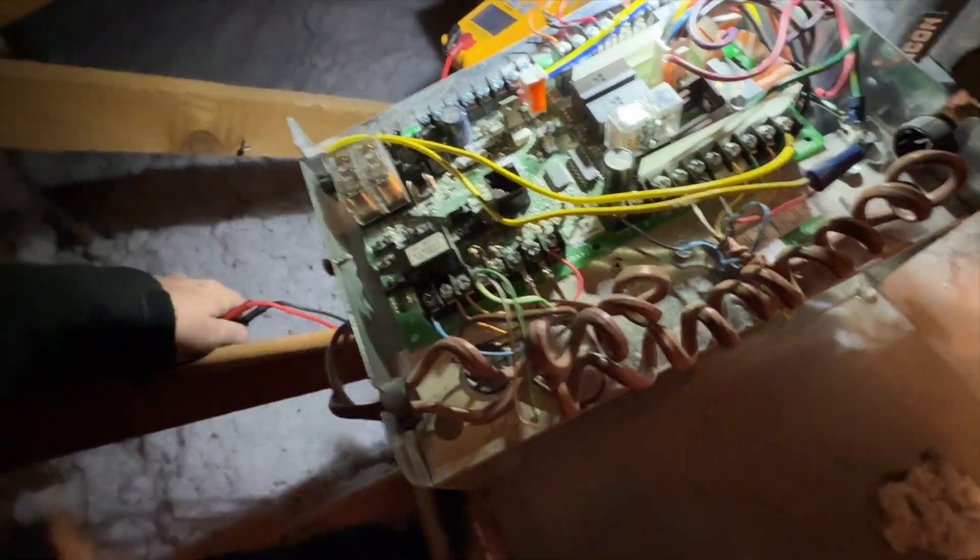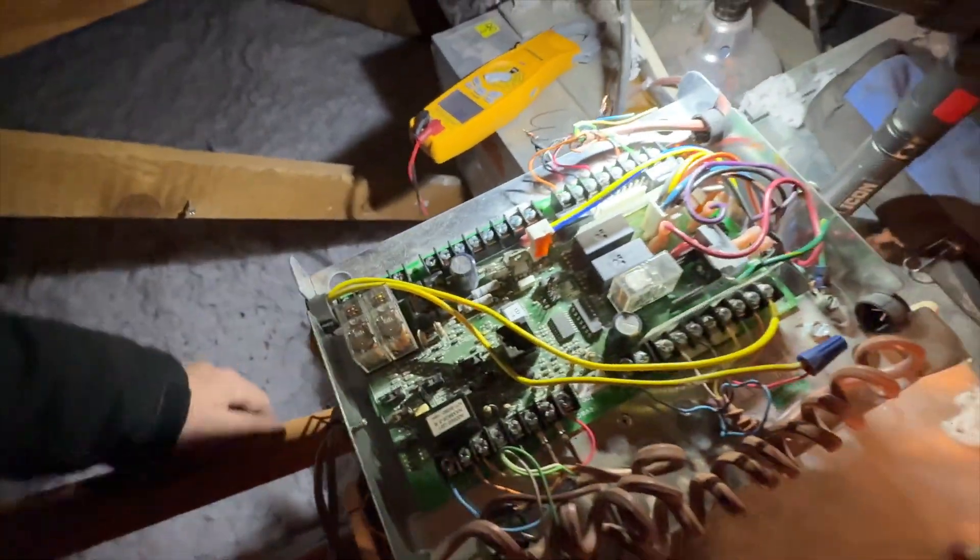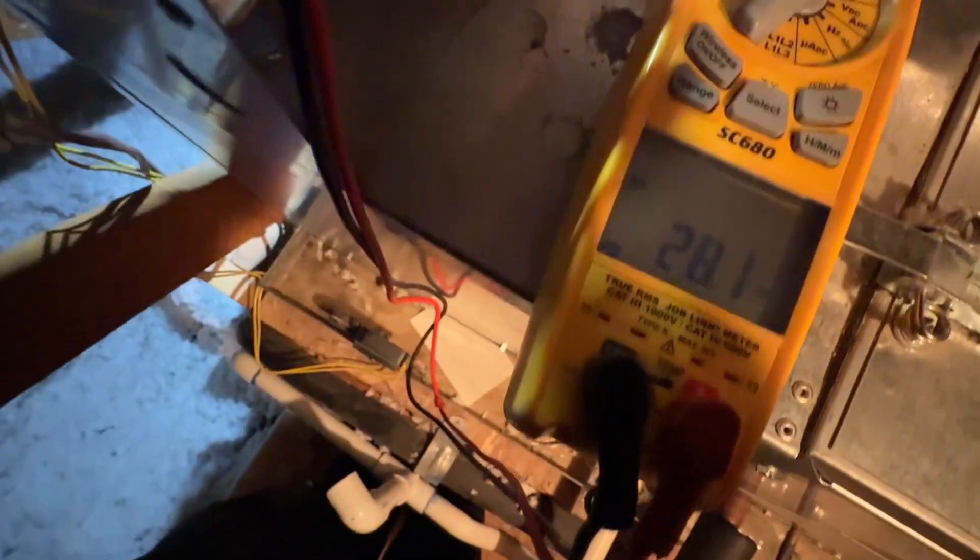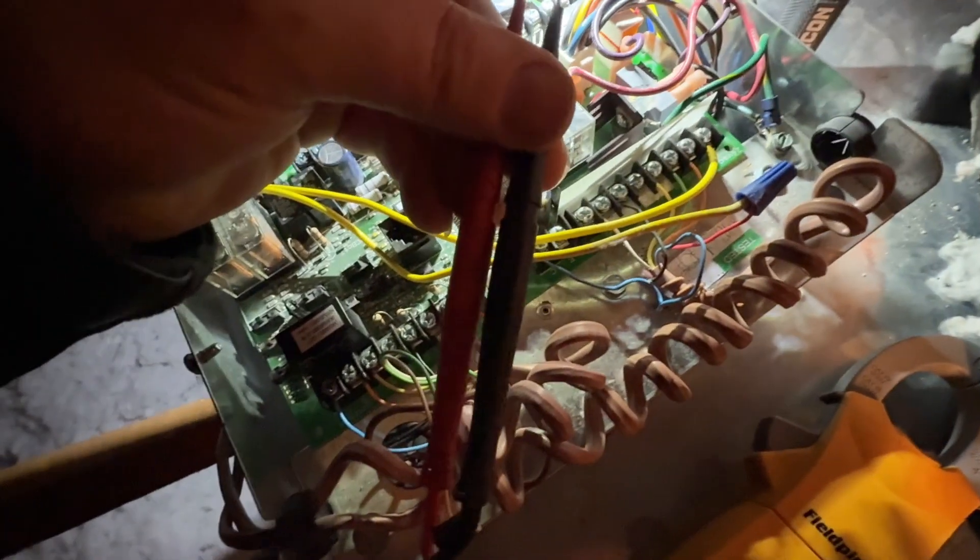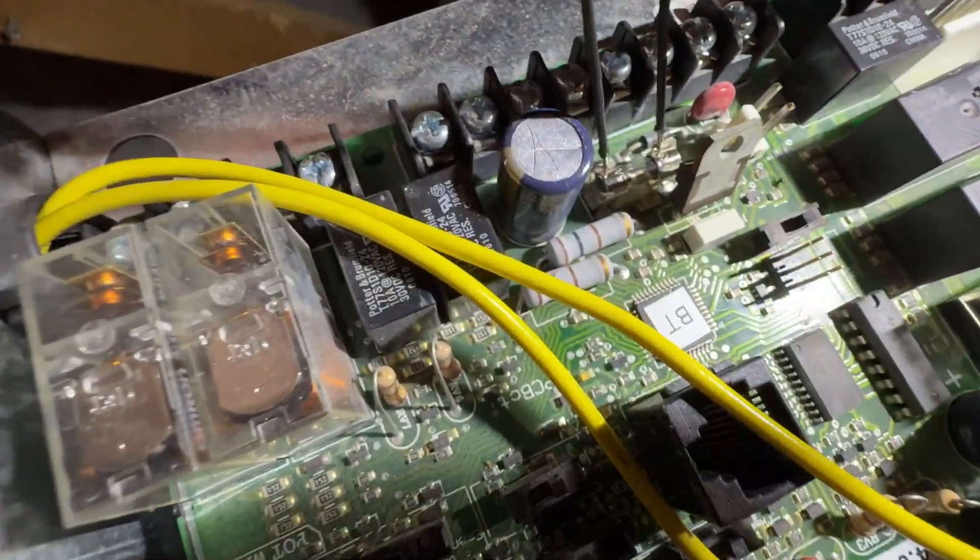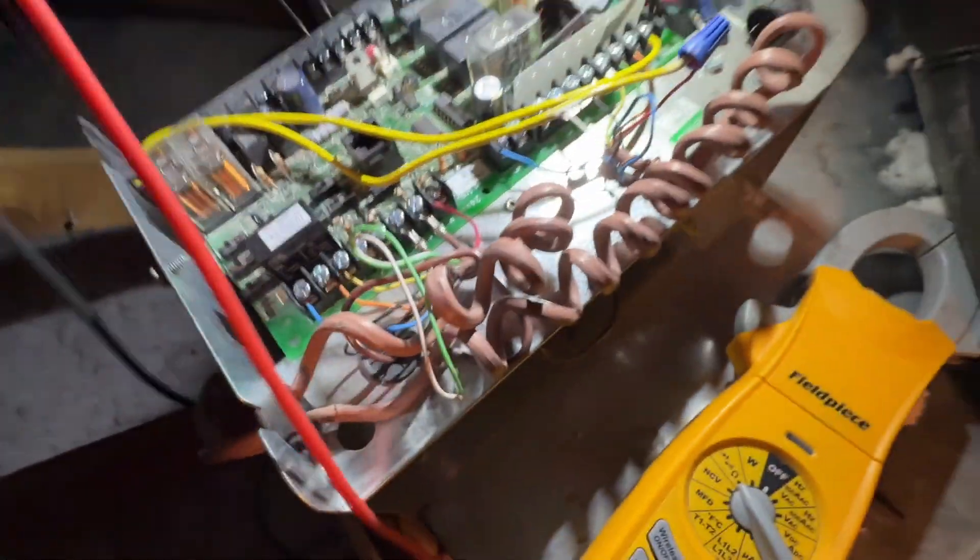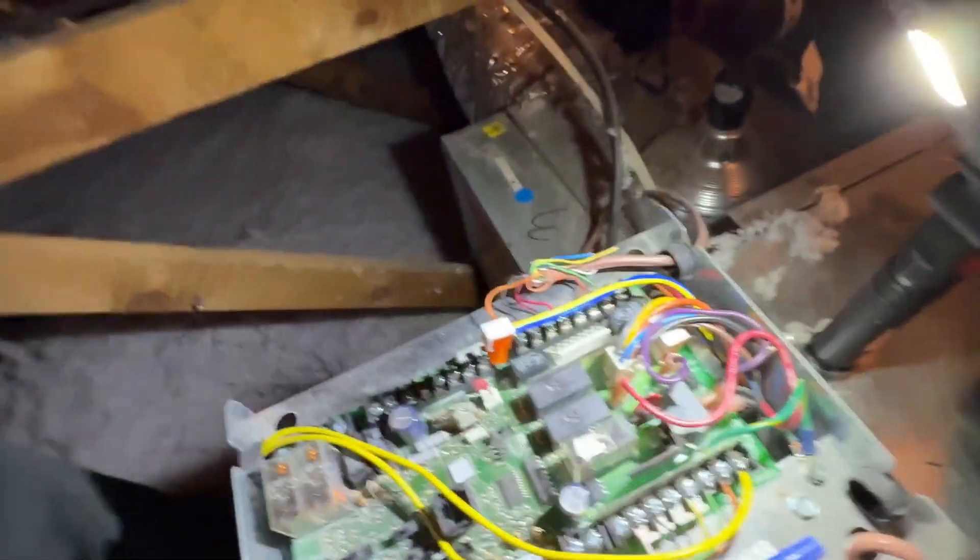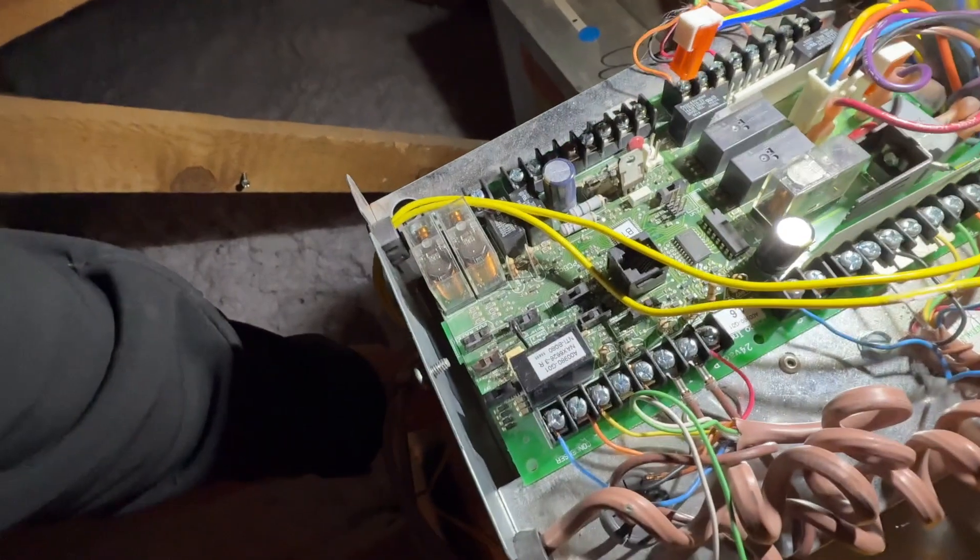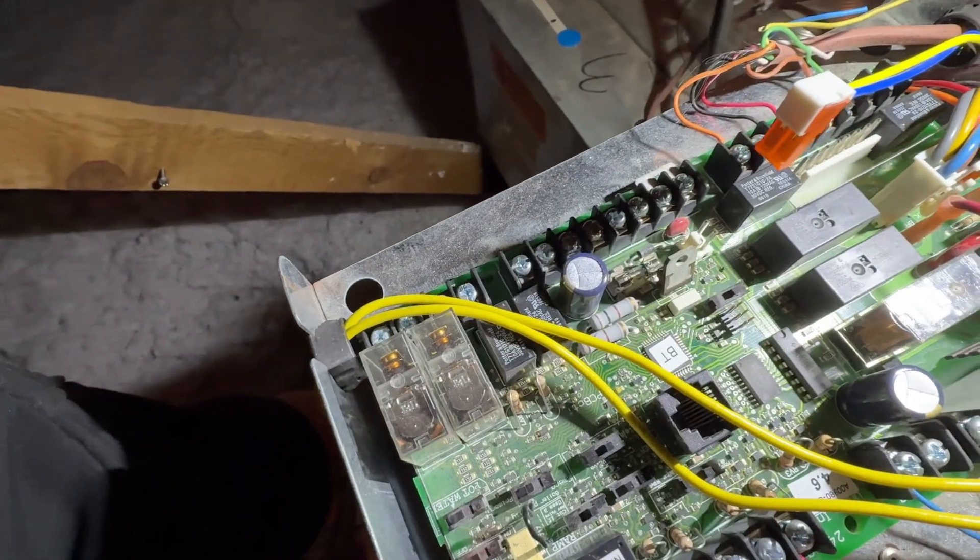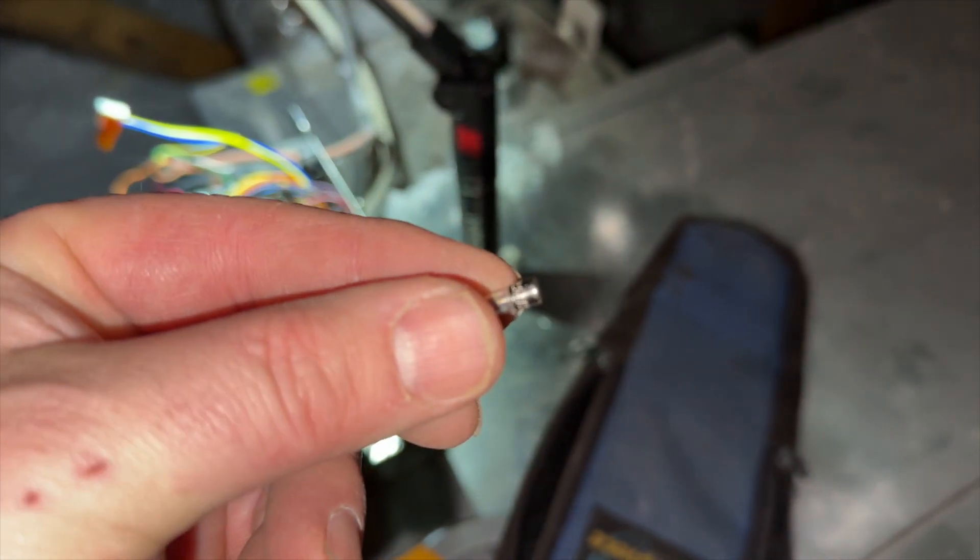I need to find out why we have no low voltage. So this cord here goes directly to the transformer, it's the secondary side. I do have voltage, so there's a problem in the board. There's probably a fuse somewhere, so we got to find it. All right, so we have a little tiny glass fuse here. I'm on continuity, it's not toning, so that fuse is bad. So now we got to see if there's a short because I don't even know where I'm going to get that fuse.